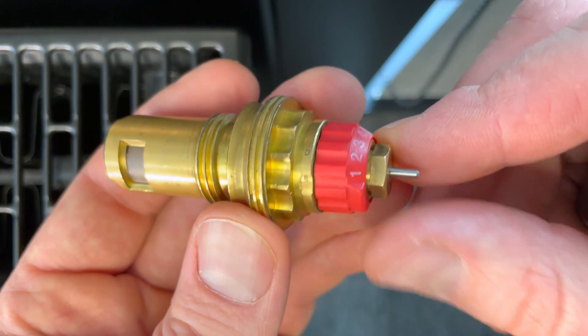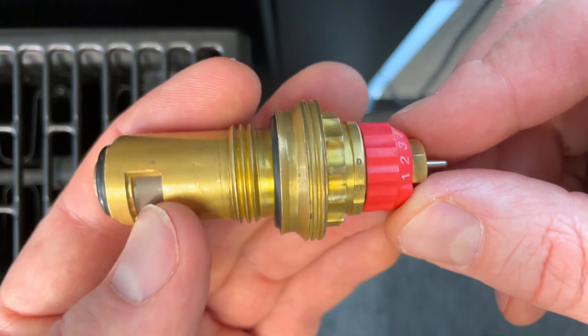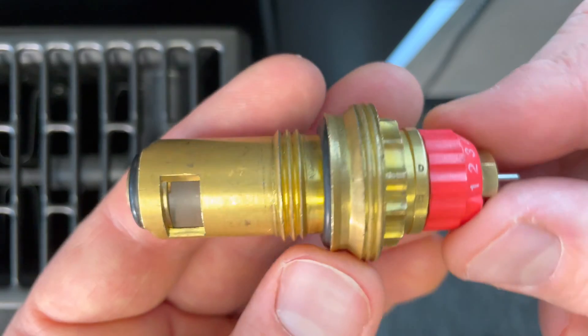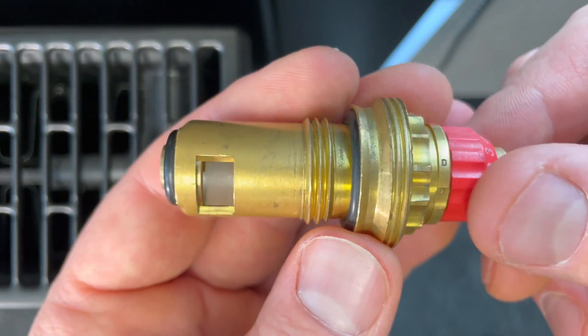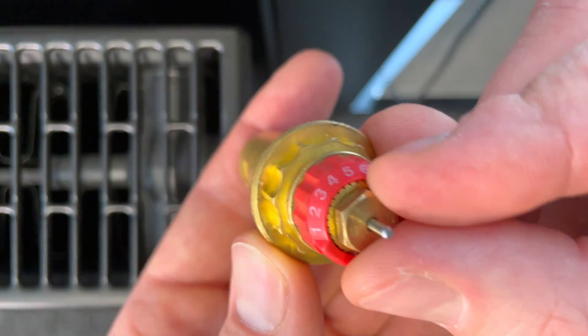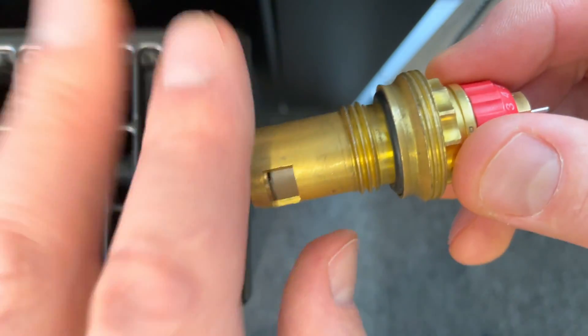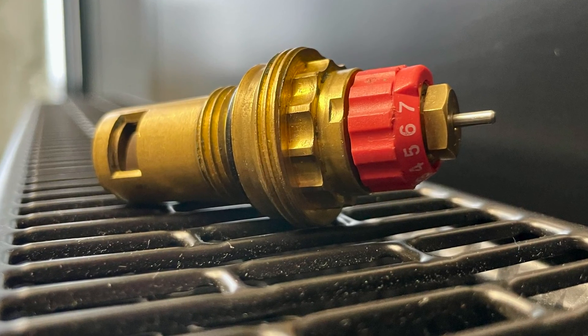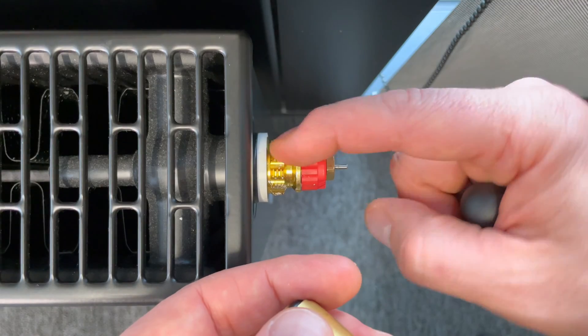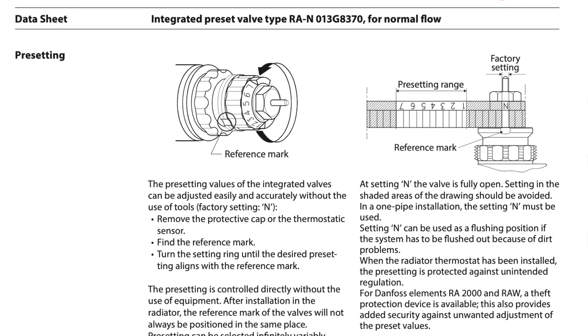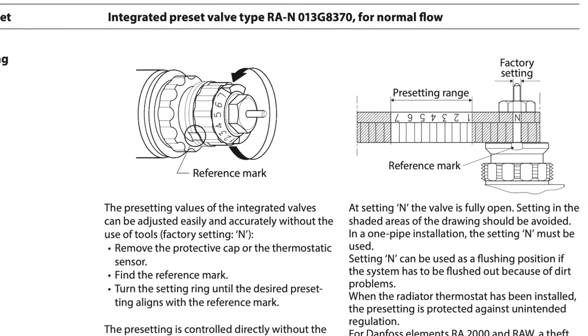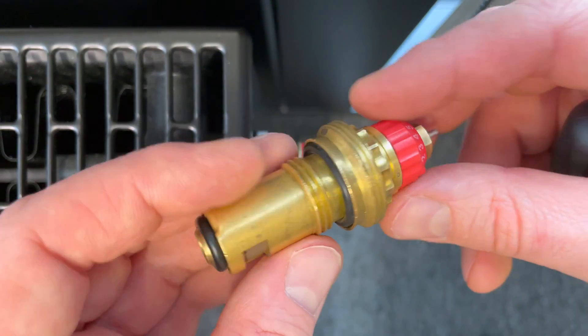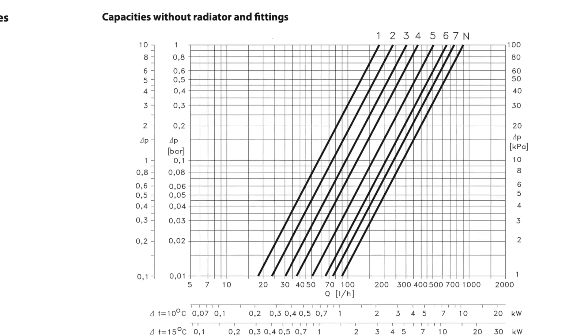Of course, too much flow is not good because you may have some noise. Too low is also not good because there will not be enough heat. So this pre-setting should be set according to your radiator capacity. Sometimes producers pre-set integrated valves from the factory; sometimes you need to do it yourself.